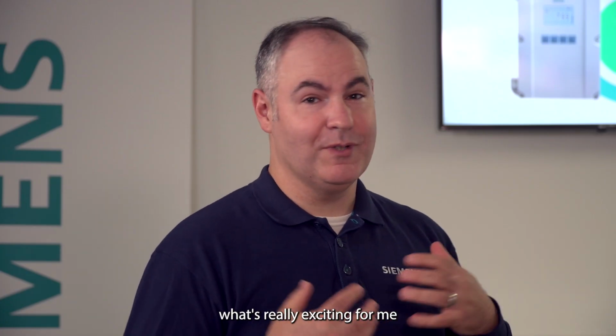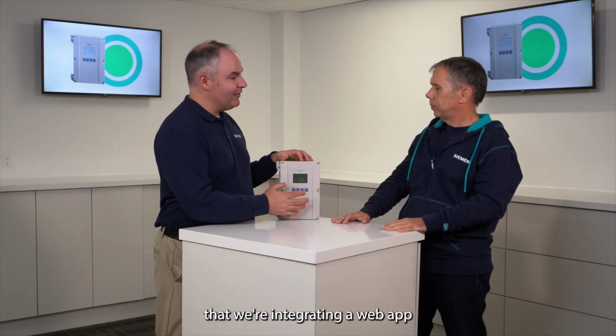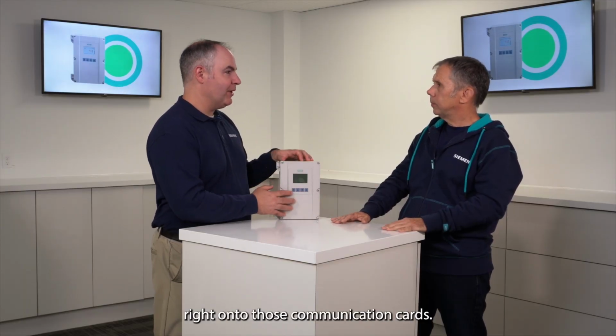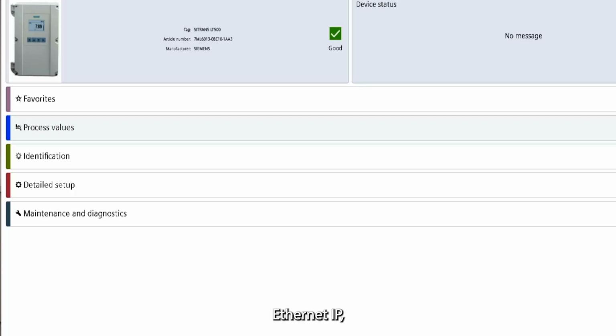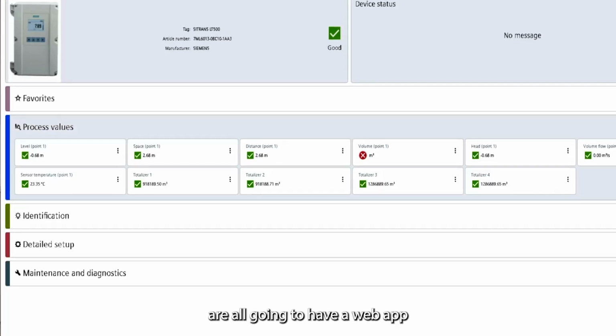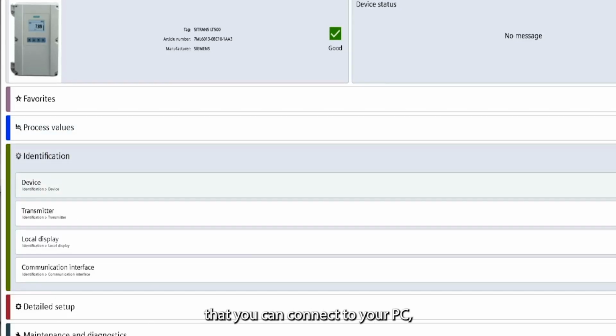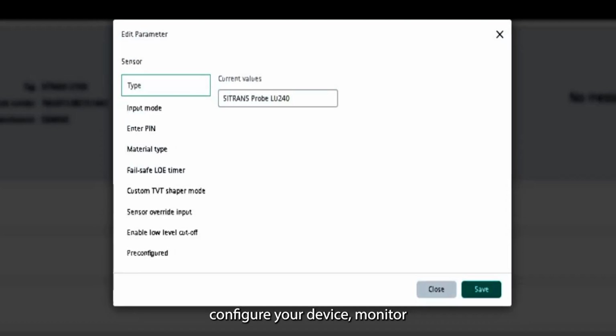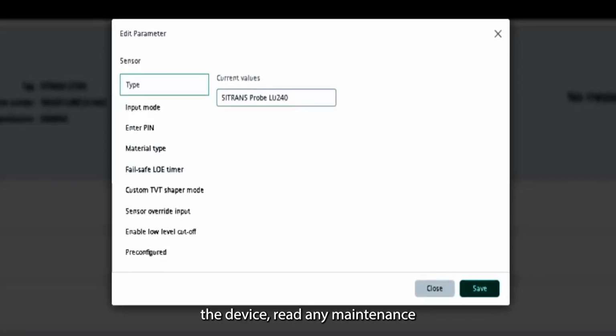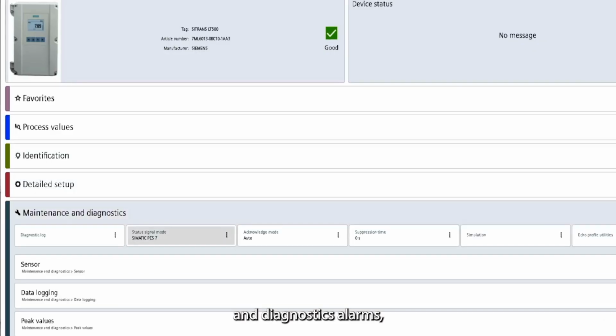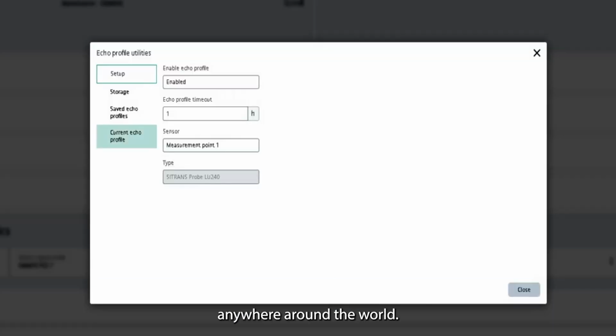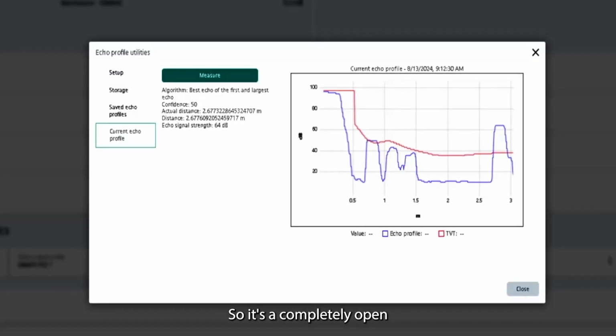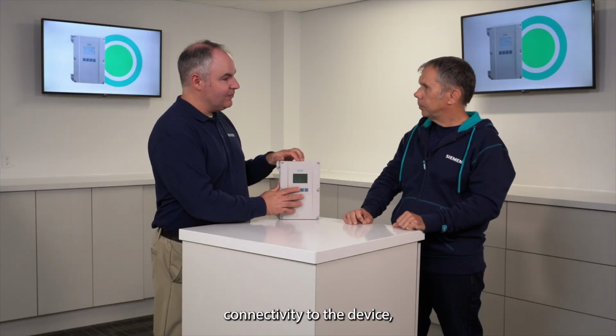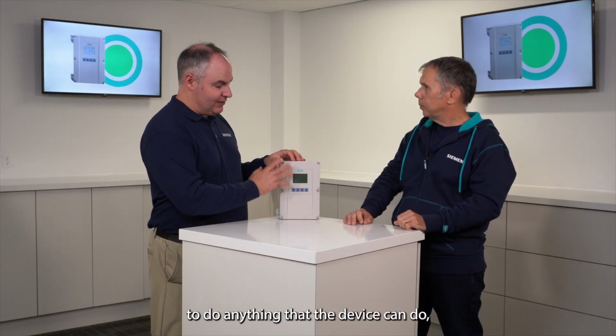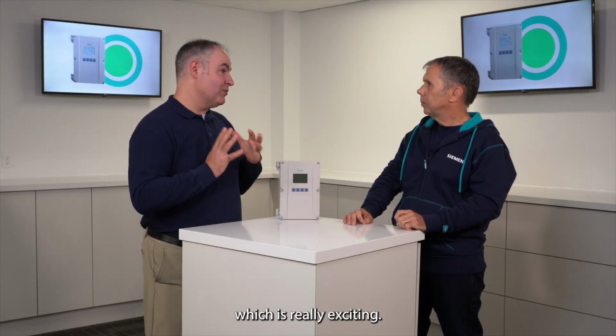And on top of that, what's really exciting for me is the fact that we're integrating a web app right onto those communication cards. So Profinet, Ethernet IP, and Modbus TCP are all going to have a web app right on the card that you can connect to your PC, configure your device, monitor the device, read any maintenance and diagnostics, alarms, and you can do that anywhere around the world. So it's a completely open and transparent connectivity to the device, and it allows you to do anything that the device can do, which is really exciting, and you don't need any additional software.